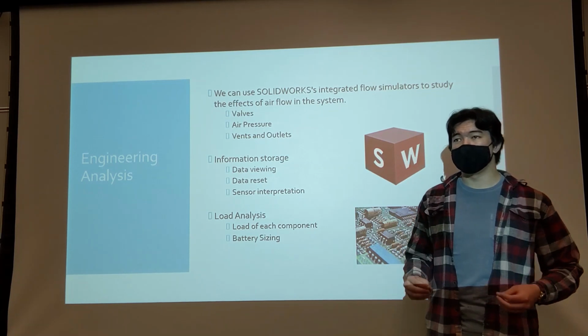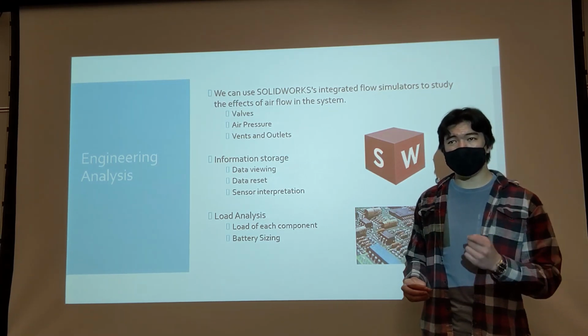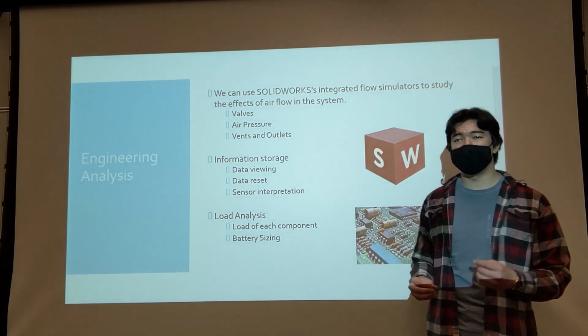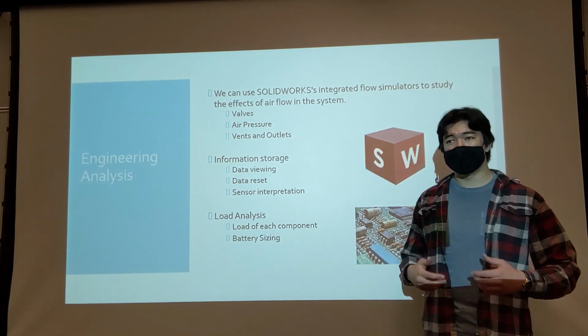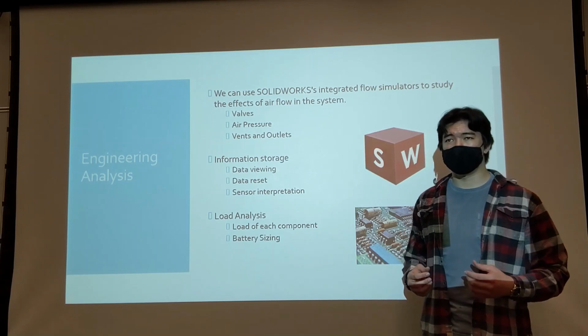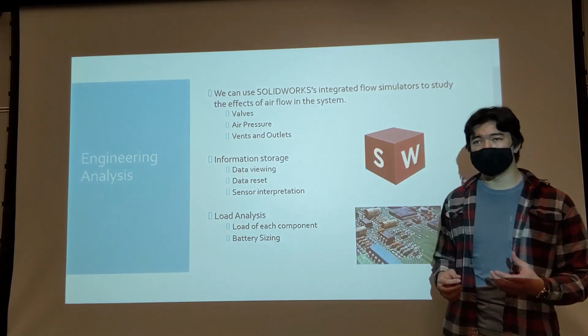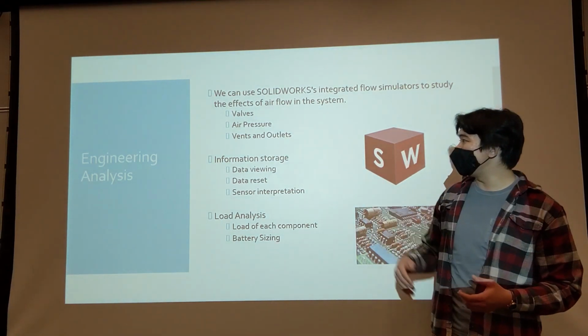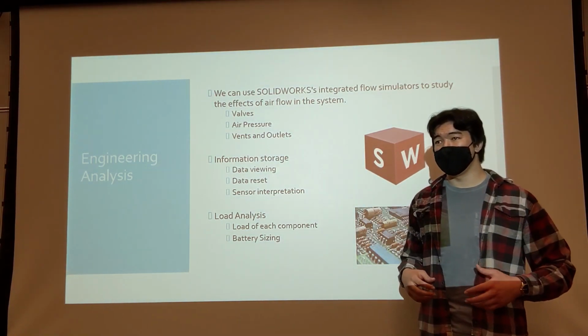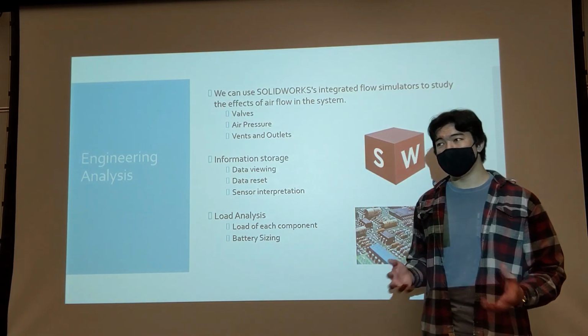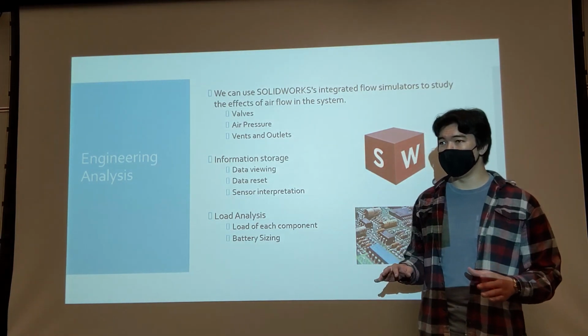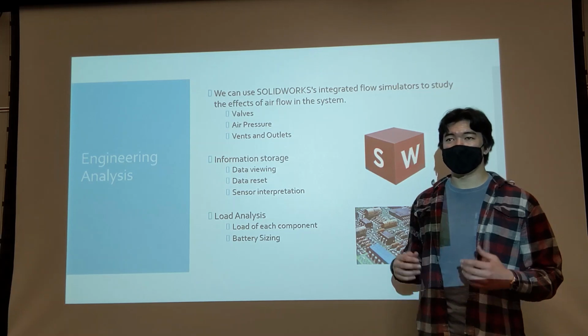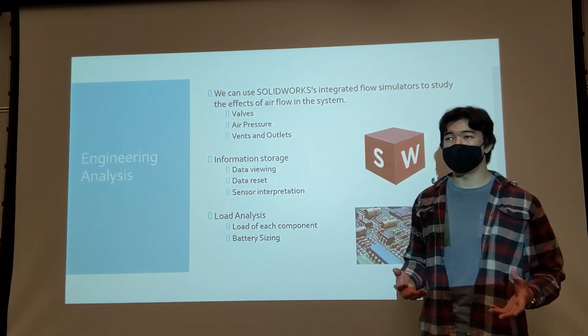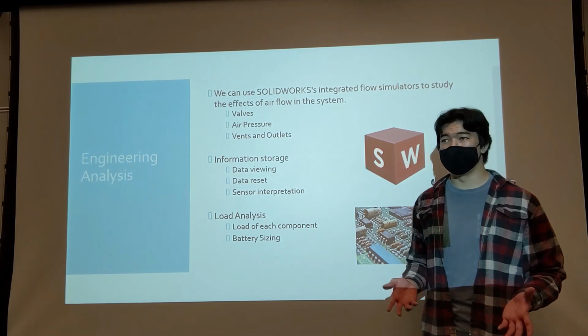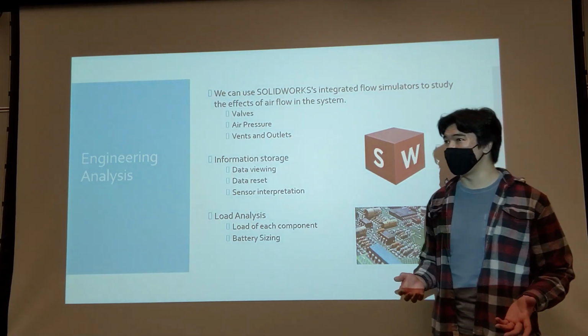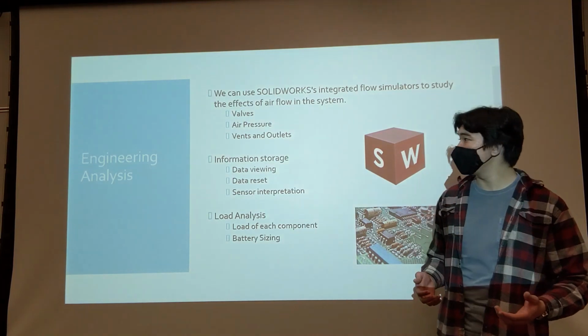But for the exhalation portion, as it goes to the OPEP device, we need to make sure that the air resistance provided by the OPEP device is sufficient so that the patient can properly exercise their lungs as they exhale. Finally, the vents and outlets. We need to make sure that all this air going through the device is exited and distributed outside the device. We don't want the diaphragm to fill with air permanently, and we don't want the patient blowing into a dead end of the OPEP device, which will make it essentially useless.